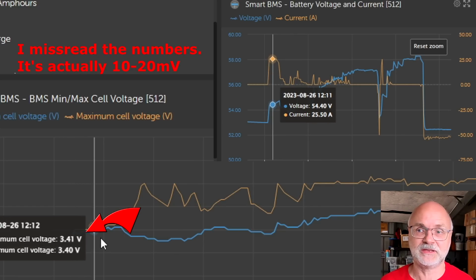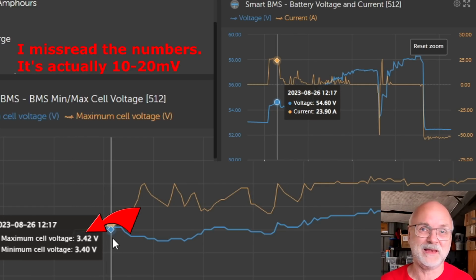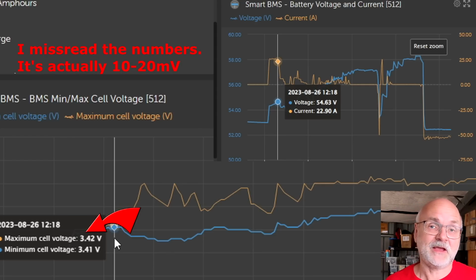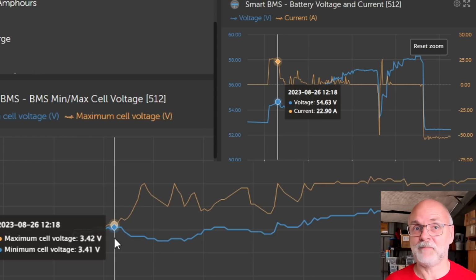Even while charging, it was only 1-2 millivolt difference. So you cannot actually tell if your battery is balanced just by looking at the minimum and maximum cell voltage - you have to charge to a higher state of charge. We can see at 54.6 volts it's not high enough, still no deviation - only 1 millivolt difference between the cells.